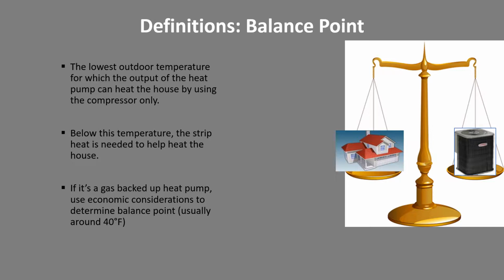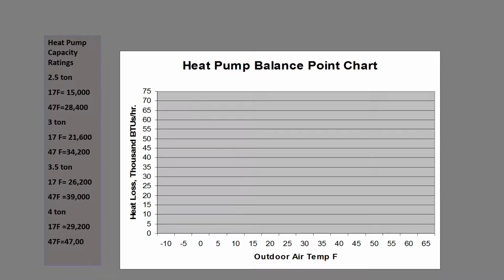If it's a gas backed up heat pump, usually it's economic considerations, price of gas versus the price of electricity, etc. Usually it's down to 40 degrees. So this is sort of an old school heat pump balance chart. The first thing that you do is that you do the heat loss calculation for the house, and you draw a line down to 65 degrees. And sure enough, the warmer it is outside, the less BTUs we have to pump into the house to maintain comfort.